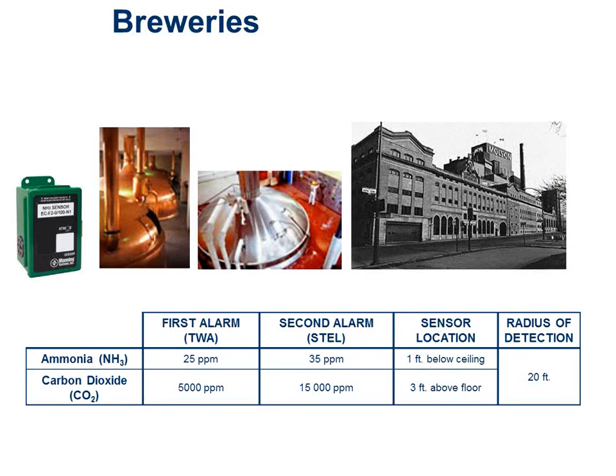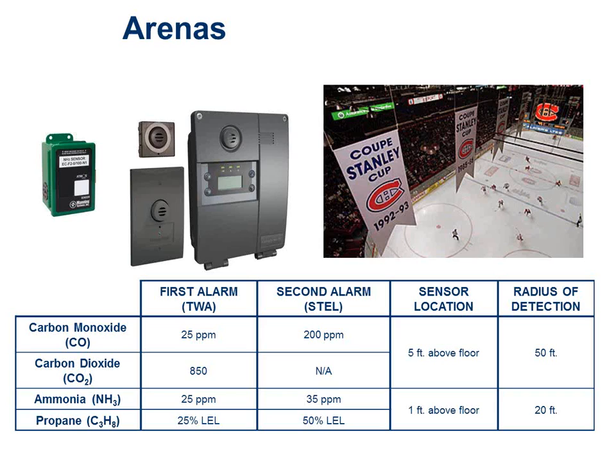Carbon dioxide is about the same weight as air, so we measure it at the breathing zone level. Arenas I mentioned before, we've got ammonia chillers in most cases, so I want to have that ammonia sensor in the chiller room. I want carbon dioxide in the spectator arena for the purposes of ventilation control. You'll notice with carbon dioxide, though, we do not have a 15-minute maximum exposure because it is not considered a harmful category of gas, right? I'm controlling it for ventilation reasons, not for safety reasons, right?